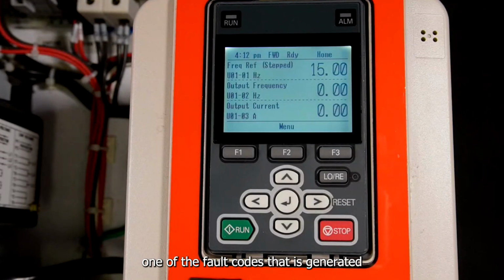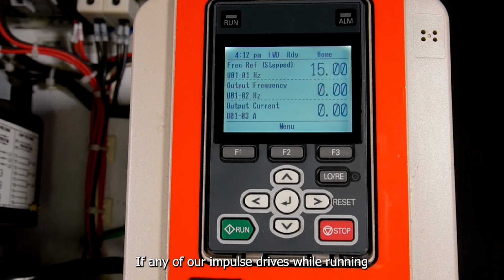In all of the Impulse drives, one of the fault codes that is generated if there's a problem on the output, the T leads to the motor, is an LF fault. If any of our Impulse drives, while running, sense the loss of one of the three T leads between the drive output and the motor, the drive will trip instantaneously on an LF or output phase loss fault.